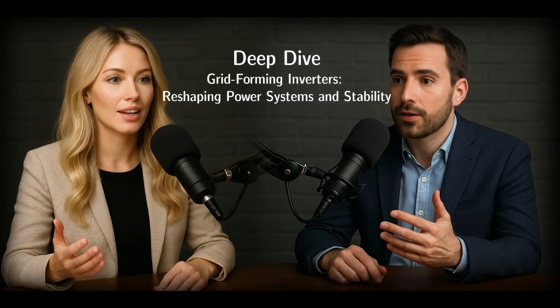Okay, so if they're followers, what other key technical traits do engineers need to know, especially regarding stability? Well, the control mode, as I said, is current source, tied to that PLL synchronization. A major implication is that their performance really degrades in weak grid conditions. Weak grids meaning areas far from those big generators. Correct. Areas with low short-circuit ratio. In those conditions, grid-following inverters can struggle, sometimes even leading to instability. Then there's fault response. Their contribution during a fault is quite limited, usually only about 1.2 to 1.5 per unit.